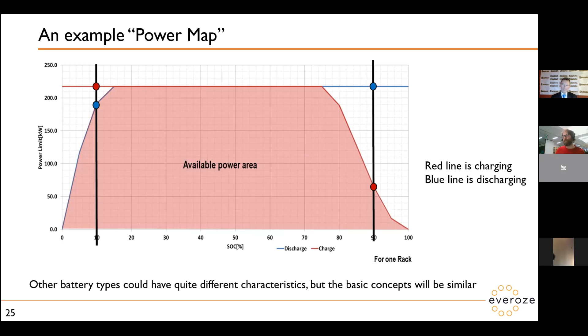You might well get a 6 kilowatt hour domestic battery. That does not mean that you can have 6 kilowatts for an hour. It will likely mean that you'll have to run it at a fraction of that for a much longer period to get all of that 6 kilowatt hours out of it.